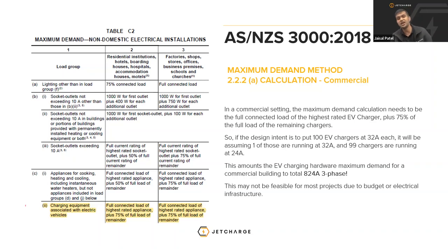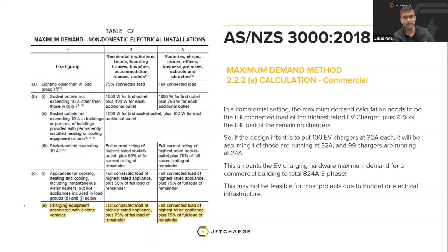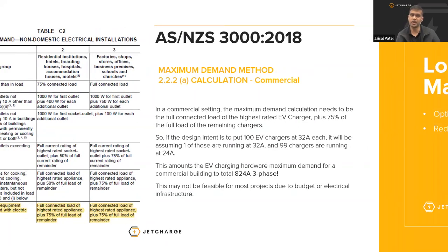This amounts to the EV charging hardware max demand for a commercial building totaling 824 amps three phase, which essentially means that you would probably have to design a whole main switchboard just for EV charging. It means that your substation may require a secondary transformer because it's possible that you may be doubling, if not tripling, the site's maximum demand, which any electrical engineer would know is a very painful exercise and typically is not feasible for most projects due to budgetary or electrical infrastructure constraints. Next slide. So there is a solution to this, load management.